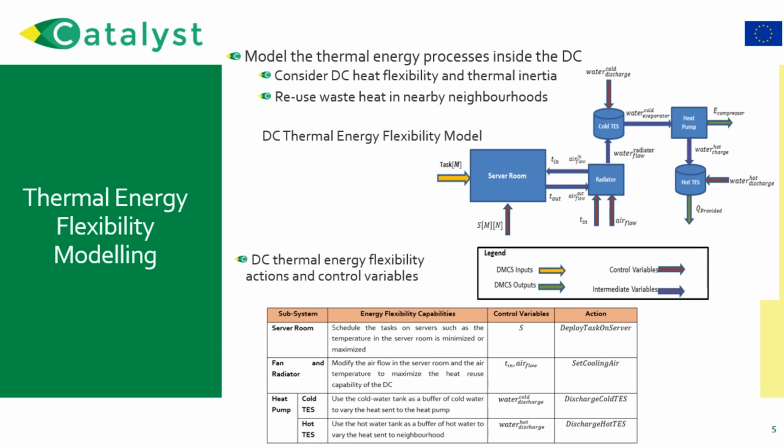To avoid these risks, before making any decisions, a simulation should be performed to validate the new temperature set points and workload distribution of the IT servers, eliminating the risks of hotspot formation and equipment malfunction. Our solution is to use methods that are based on computational fluid dynamics, which feature numerical simulations to compute the flow of fluids in an area defined by boundary surfaces, which is in our case the server room.